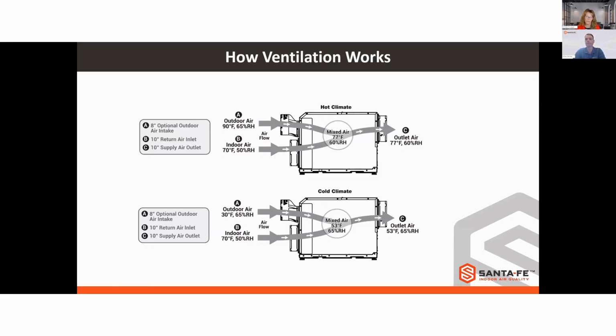Now, when you set up the ventilation schedule on the dehumidifier, either using our GH3000 controller or another ventilation device, it's going to activate the fan for ventilation. It's not going to automatically activate the compressor of the dehumidifier when we're ventilating. So our air conditioning might be running long enough during that period of time that bringing in that potentially hot, humid air is not going to affect the relative humidity in the home.